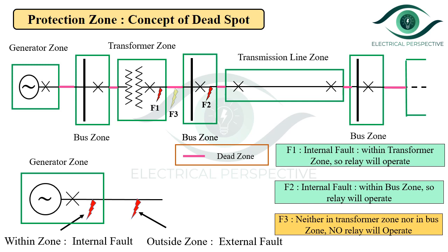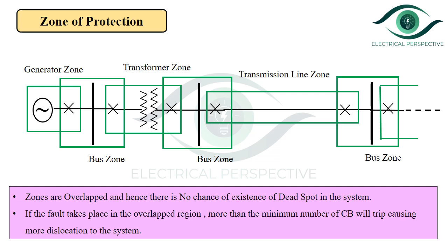No part of the system should be left unprotected. To avoid dead spots, adjacent zones are overlapped so that there is no chance of a dead spot existing in the system — meaning no part of the system will be left unprotected due to overlapping. However, if a fault takes place in the overlap portion, then more circuit breakers get tripped than the minimum necessary to disconnect the faulty element. The extent of overlapping of protective zones is relatively small, and thus the probability of a fault in the overlap region is also very low. Consequently, the tripping of too many circuit breakers will also be infrequent.